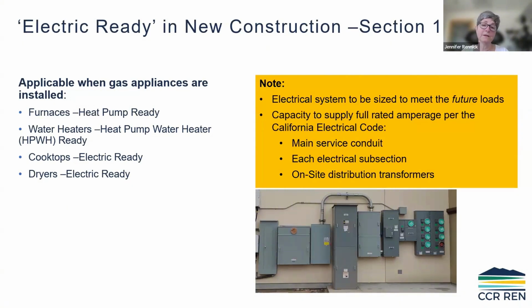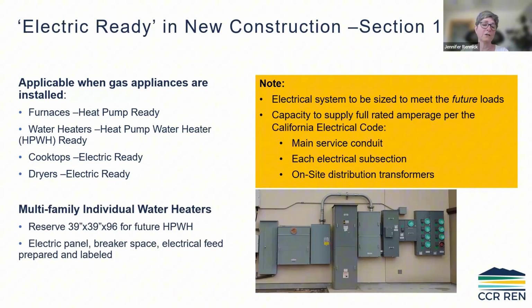The electric ready is, again, for new construction. If you install a gas appliance like a furnace, then you've got to make the space heat pump ready. And if you install a water heater that's a gas appliance, then it needs to be heat pump water heater ready. For cooktops, it can be electric ready in general, any kind of electric, and dryers, any type of electric ready. And then the new code language spells out that for multifamily projects, when you have individual water heaters, you have to reserve a space that's 39 inches by 39 inches by 96 inches for a future heat pump water heater.